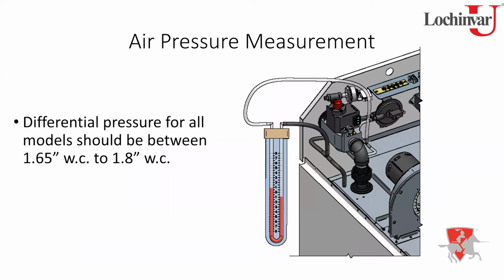Now, realistically, the pressure on the burner, that little barb, that pressure there should be a negative. All right, because you've got air going through that burner, it should be pulling a negative at that point. Very slight negative. So I'm looking for a differential between 1.65 to 1.8 inches. That's a little on the high end, but 1.65 to 1.8 is what I'm looking for here.